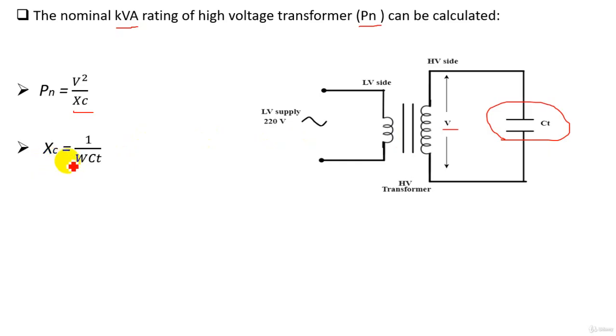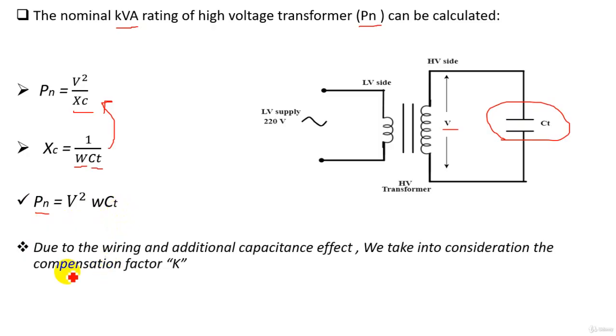We know that Xc equals 1 over omega Ct, while omega is the angular frequency and Ct is the capacitor of the specimen or the insulator to be tested. By substituting the value of the Xc in this equation, we find that Pn, the rating of the transformer, equals V square omega Ct. But we should take into consideration another compensation factor K due to the wiring and additional capacitance effect. This is for safety factor.